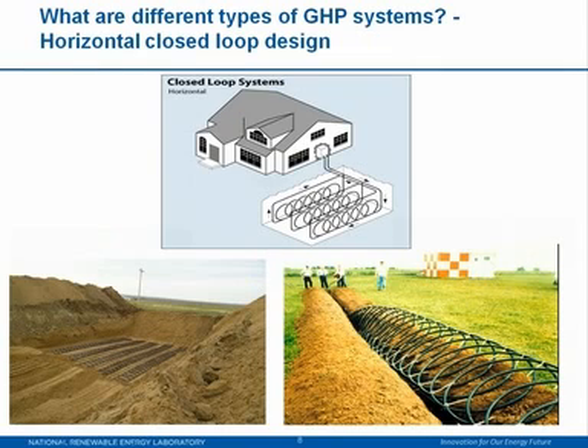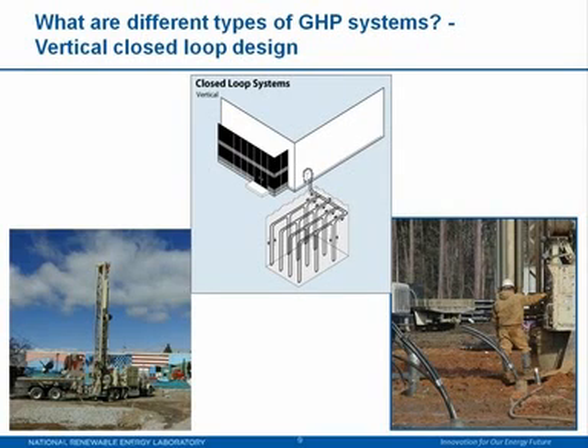The next type of closed-loop ground source heat pump system is a vertically oriented closed-loop design, where you're drilling boreholes or wells deeper into the earth—we're talking 150 to 400 feet deep—and the piping is then inserted into those boreholes.